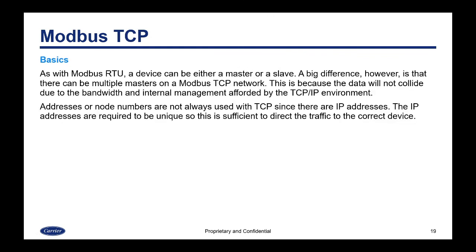With Modbus TCP, as with Modbus RTU, a device can either be a master or a slave. A big difference, however, is that there can be multiple masters on a Modbus TCP network. This is because data will not collide due to the bandwidth and internal management afforded by the TCP/IP environment.